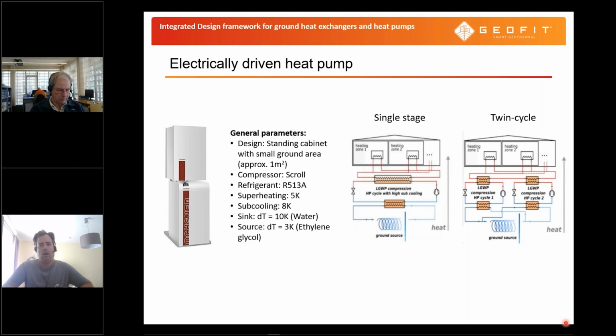For instance, dealing with a retrofit use case, a favorable heat pump configuration can be a twin cycle, which is shown on the right here. A twin cycle configuration is basically two heat pumps in series on the supply side and in parallel on the source side, on the ground source side. So with two heat pumps, you are able to have a performance and an efficiency increase to a certain amount. But of course, it's two heat pumps compared to one heat pump, to a single stage heat pump.